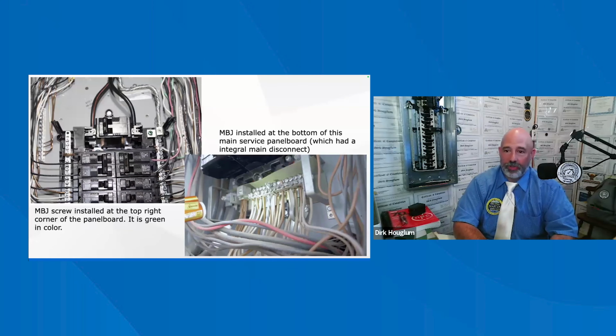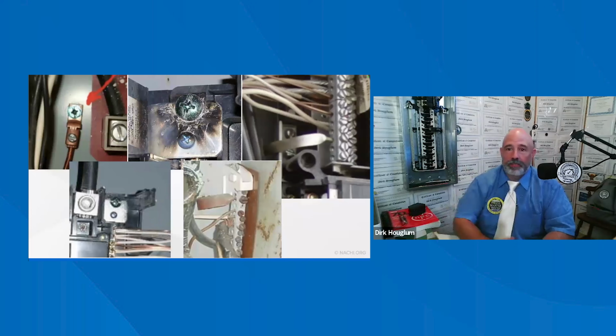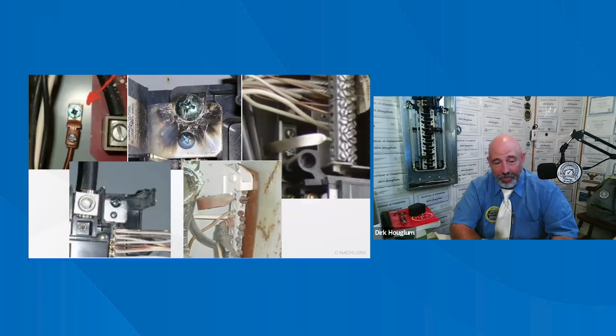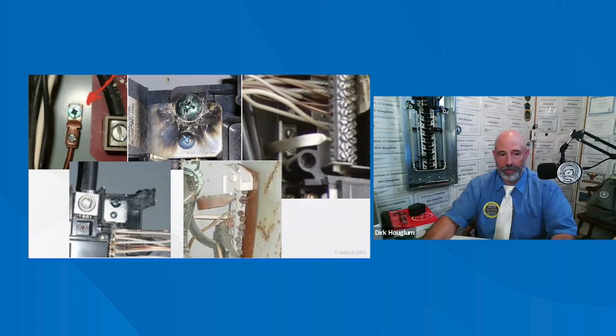If it is used as service equipment, main panel, that is, the neutral conductor bus bar must be bonded to the enclosure. If it is not used as such, then it has to be isolated or separated from it. The inspector image shows several types of panel board bonding. Some are straps and some are screws. So I'll give you a few seconds to kind of look at that. See a little bit of overcurrent there on that one picture.